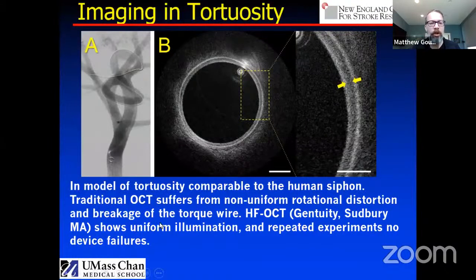And this is probably the most important image of the slide. This image was acquired about 6 years ago, where here you can see the system operating in tortuosity. We've measured, this is the brachial artery of the pig in a maximally flexed position. And we find that if you look at these curvature and radii of curvature, they're quite similar to the human internal carotid artery siphon. So we acquire these images, and what we could see is that even in this level of tortuosity, we get a completely clear image that's artifact-free.